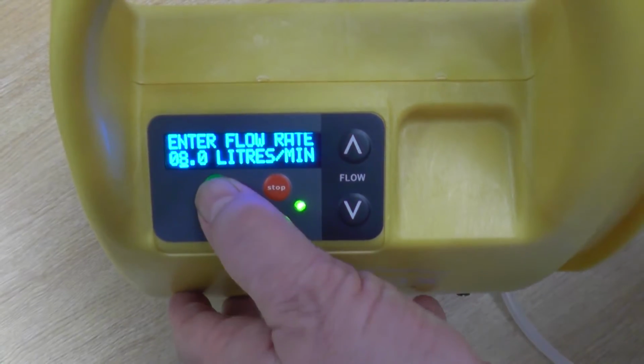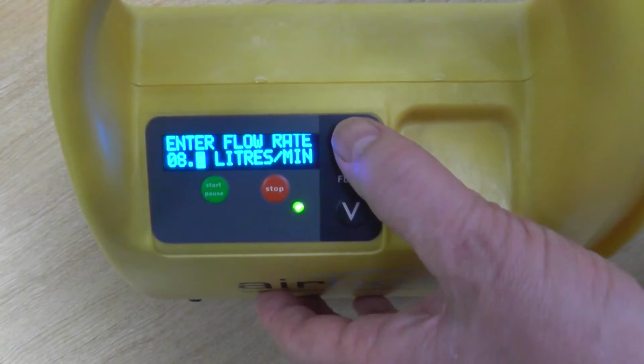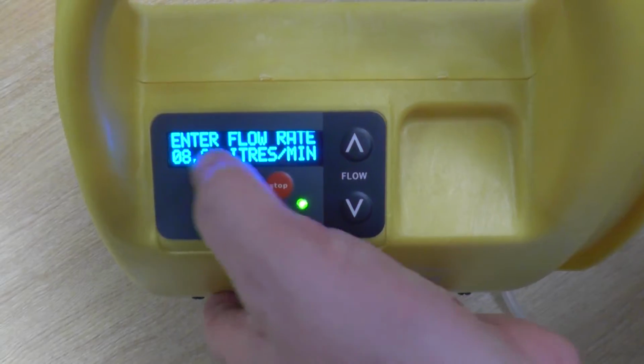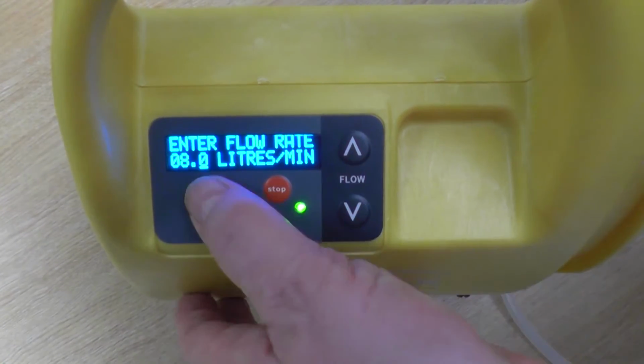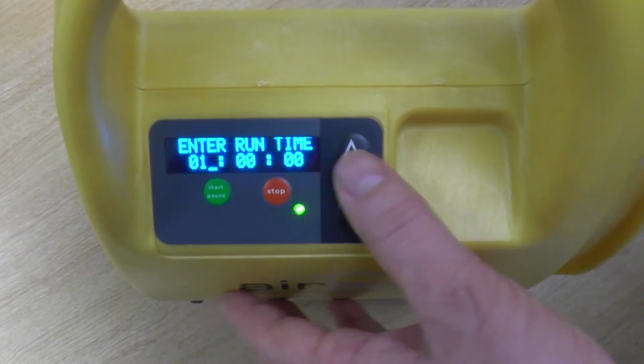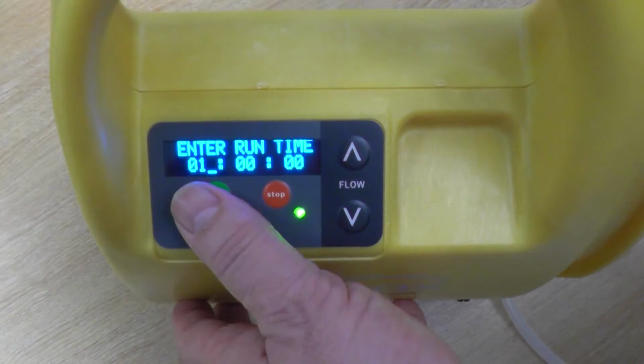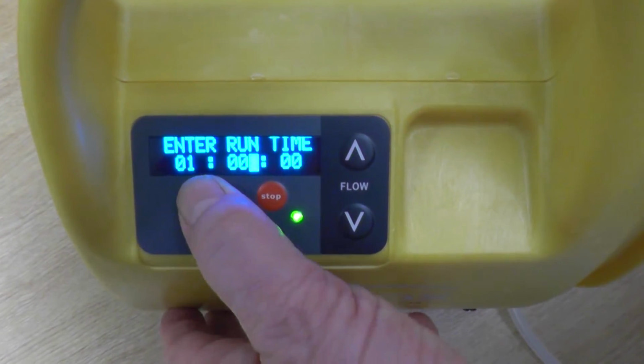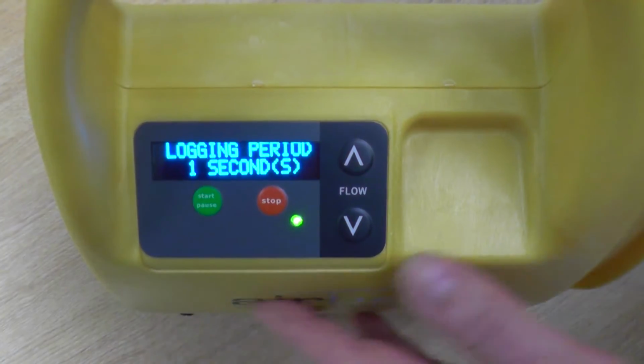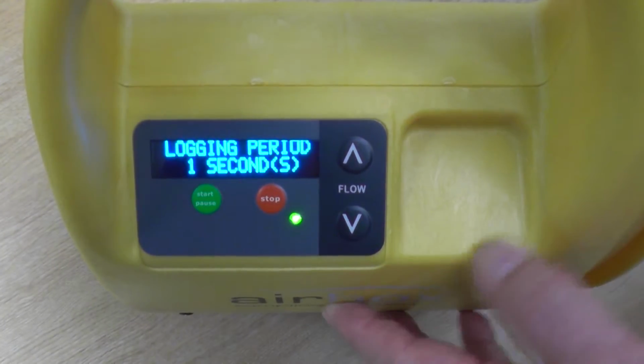We'll do 8 litres a minute, but it can be changed to anything like 8.1, up to 16 litres, and then a run time. If you run it for an hour at 8 litres, it'll collect 480 litres of air.